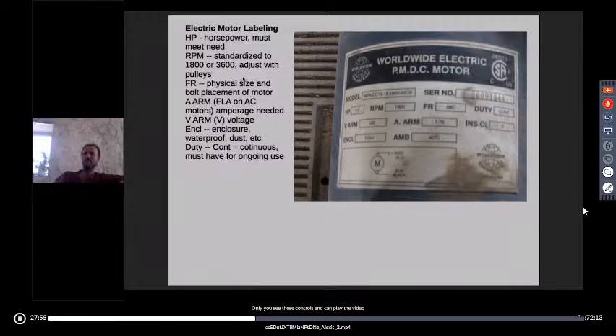Common NEMA frames for blowers and standard equipment include the 48 frame, 56 frame, and 56C. If a piece of equipment has a 48 frame motor, a DC motor with a 48 frame will have the same bolt pattern, shaft size, and shaft length. The relationship and geometry between where the motor bolts and where the pulley runs is the same, except DC motors are often longer.